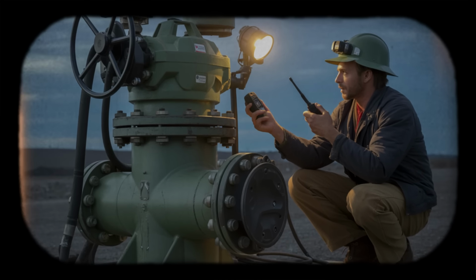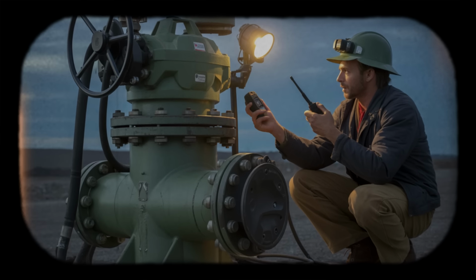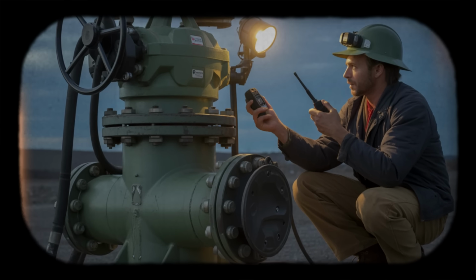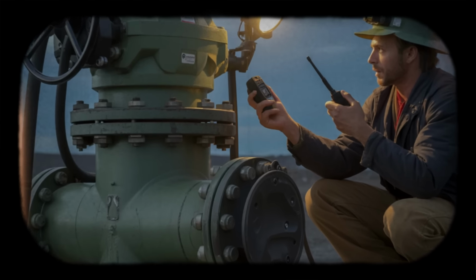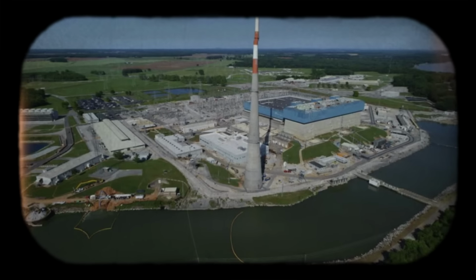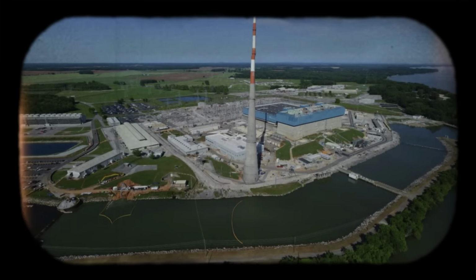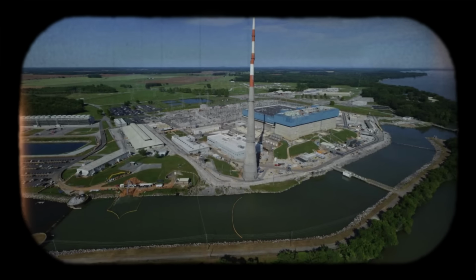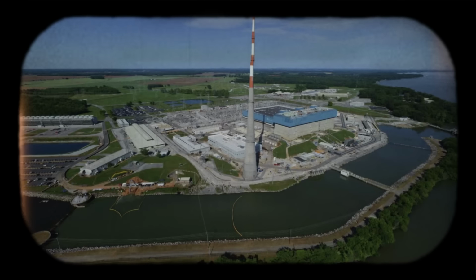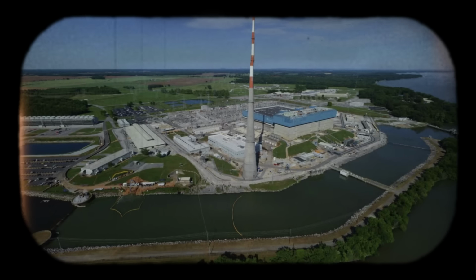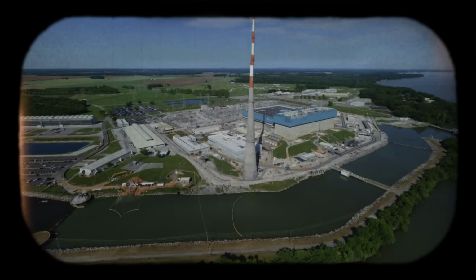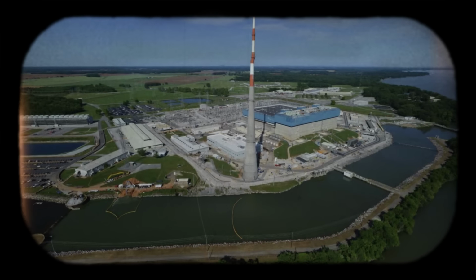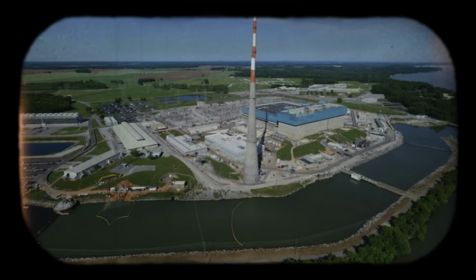If residual heat removal pumps stop, coolant temperature would begin rising at a rate determined by the thermal mass of water in the reactor vessel and connected piping. Initial calculations by TVA engineers suggested that complete loss of shutdown cooling could result in core uncovery within several hours depending on initial conditions. Core uncovery means the water level drops below the top of the fuel rods, allowing them to overheat. Overheating leads to cladding failure and potential fuel damage.